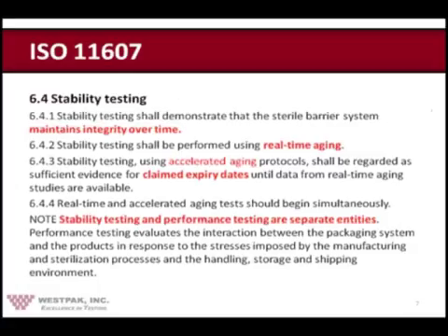It's also interesting to note that the standard specifically separates stability testing from performance testing as separate entities. That should be relatively obvious, but from that I assume that there might have been some misunderstanding about those in the past. Also note that real-time and accelerated aging studies should begin simultaneously.